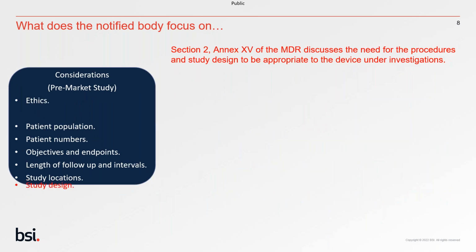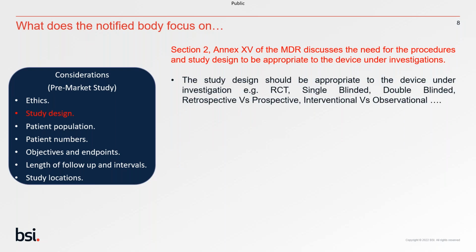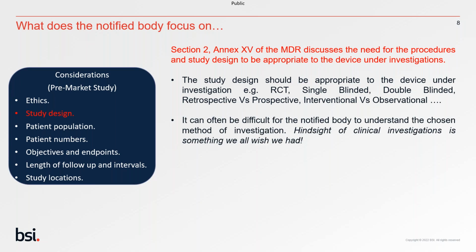Section 2, again, of the MDR talks really about study design, and it reports that Annex 15 of the MDR discusses the need for the procedures and study design to be appropriate to the device under investigation, or I should say devices under investigation, apologies. So really what we're always looking for is, why have you chosen that study design? So when reporting your clinical investigation and your clinical evaluation report, really think about the justification and what is behind the reason for considering that study.